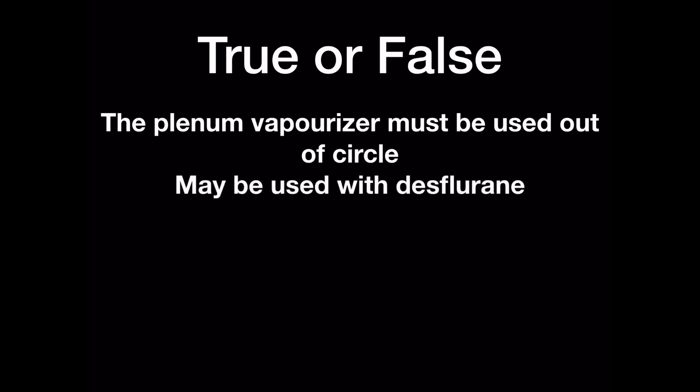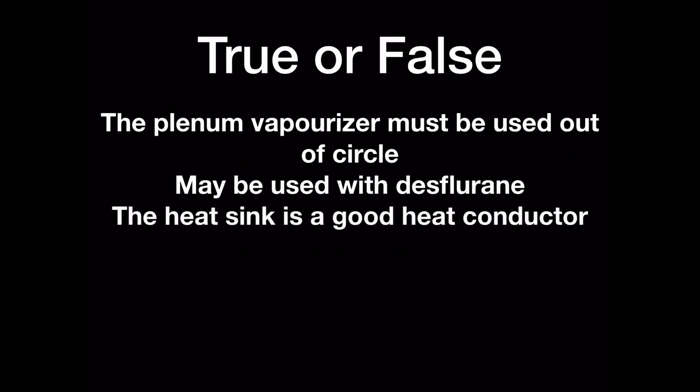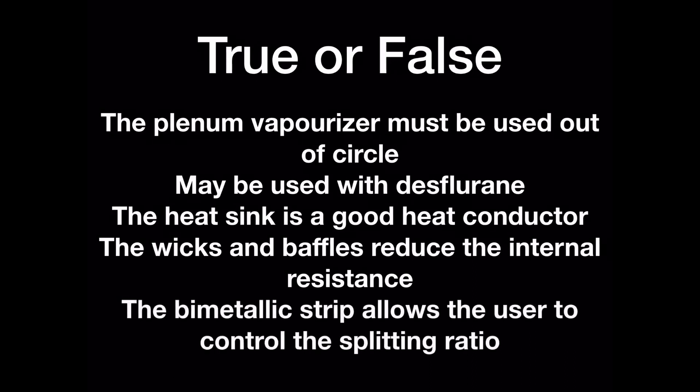Exam questions — true or false? The plenum vaporizer must be used out of circle. The plenum vaporizer may be used with desflurane. In the plenum vaporizer, the heatsink is a good heat conductor. In the plenum vaporizer, the wicks and baffles reduce the internal resistance. In the plenum vaporizer, the bimetallic strip allows the user to control the splitting ratio.